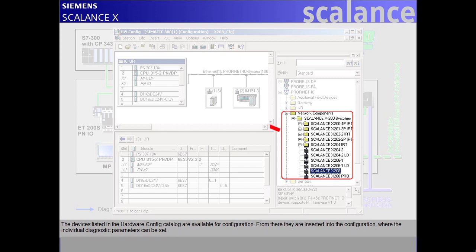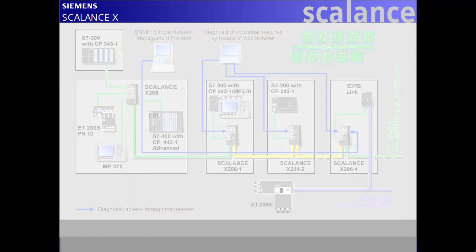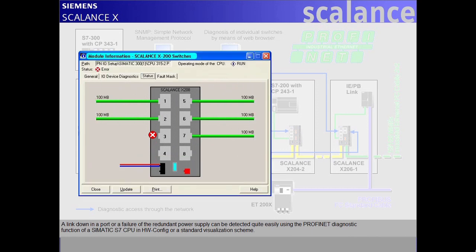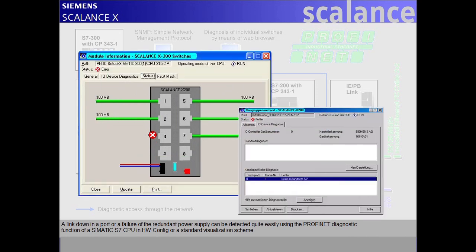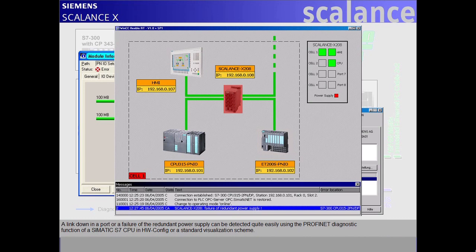From there, they are inserted into the configuration where the individual diagnostic parameters can be set. A link down on a port or a failure of the redundant power supply can be detected quite easily using the PROFINET diagnostic function of a SIMATIC S7 CPU in hardware config or a standard visualization scheme.